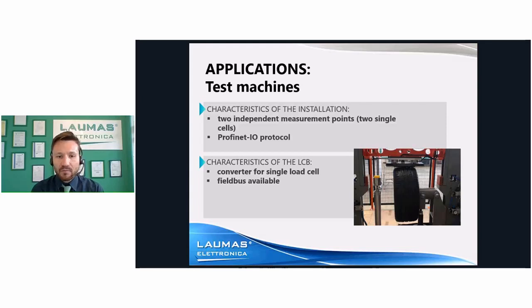In this second example, we are showing a test machine for tire testing that has two points of support, so it uses two load cells, and must measure the correct balancing of the wheel and simulate the wear of the tire solicited in many different conditions. The two force measurement points are independent from each other, so each one uses its own digitizer, and the plant obtains data from the two load cells and transmits them via Profinet IO to a PLC that handles the information.